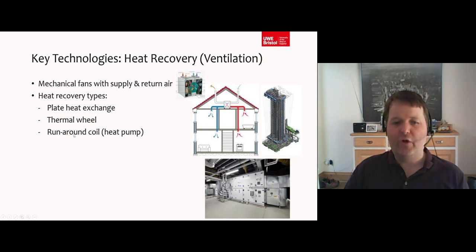A little problem with the thermal wheel. They've been banned in hospitals in the UK for a while now because of a potential issue with contaminants, colds and flus getting onto the wheel and going into the fresh air. And I imagine with the current remit, they're becoming even less popular. Although there are reputed to be techniques for making sure that doesn't happen, which are emerging. I think it'll probably become a less popular option, the thermal wheel over the plate heat exchanger.